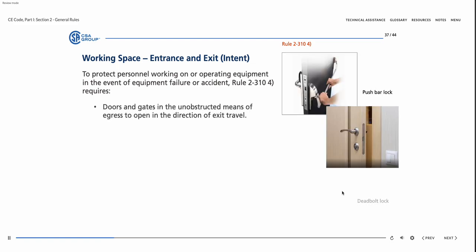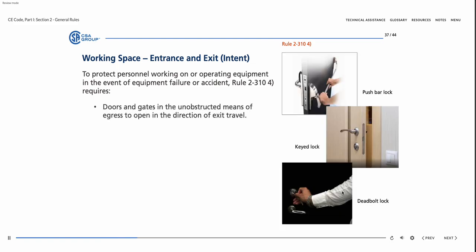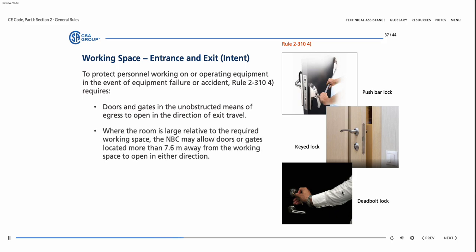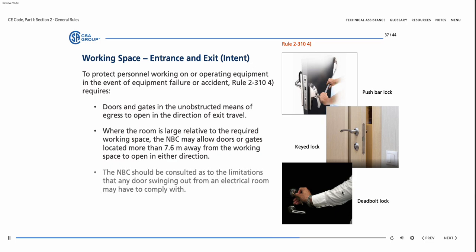However, to protect personnel working on or operating equipment in the event of equipment failure or accident, Rule 2-310-4 requires that doors and gates in the unobstructed means of egress will open in the direction of exit travel. Where the room is large relative to the required working space, the National Building Code of Canada may allow doors or gates located more than 7.6 meters away from the working space to open in either direction. The National Building Code of Canada should be consulted as to the limitations that any door swinging out from an electrical room may have to comply with.